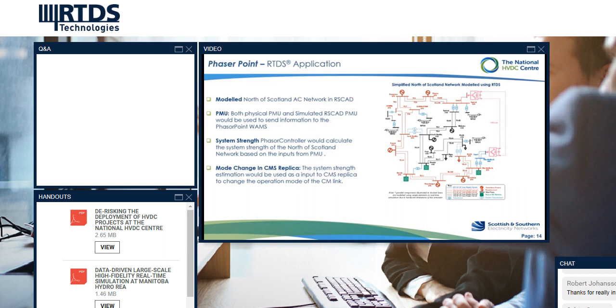These measurements from various points in the network could be used by GE's phasor controller to estimate the system strength. This estimated system strength would be used to create a digital signal, which would further inform the HVDC control and protection of CM to operate in the right mode, thus fulfilling the objective of this project.